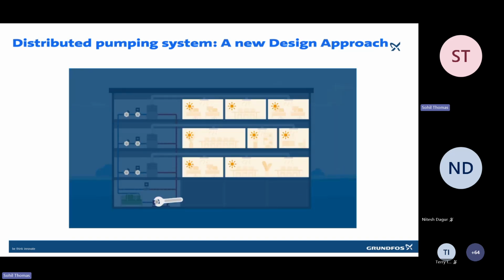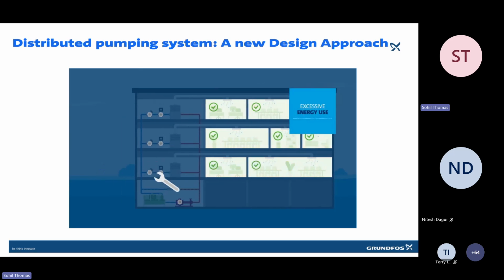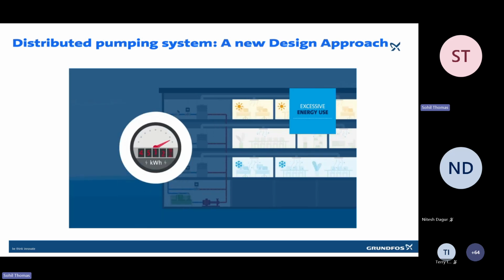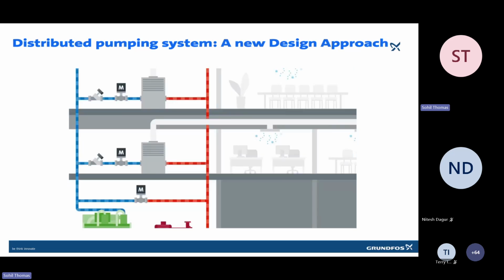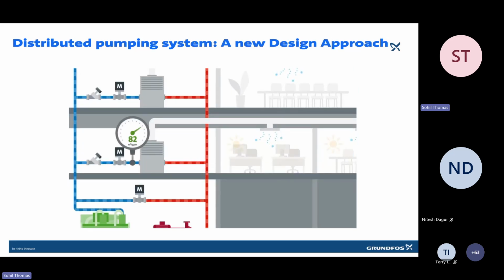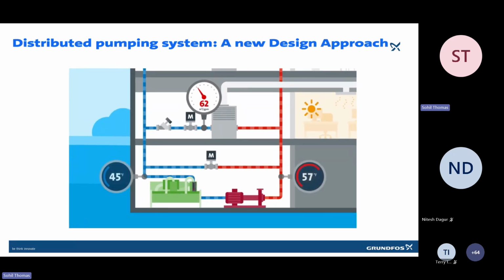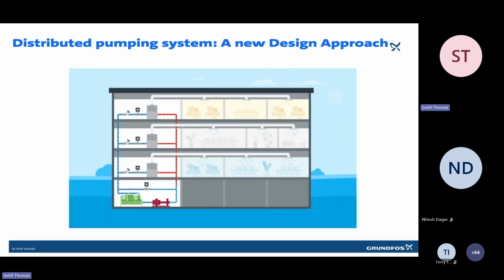One is commissioning and balancing, which is traditionally a time-consuming and tedious procedure, but essential for ensuring a system that operates to its highest potential. Inadequate commissioning leads to poorly balanced systems and excessive energy use. An incorrectly balanced system will result in having terminal units receiving more or less flow than necessary. This could also lead to low delta T. This is especially apparent at part load conditions and results in less comfort.